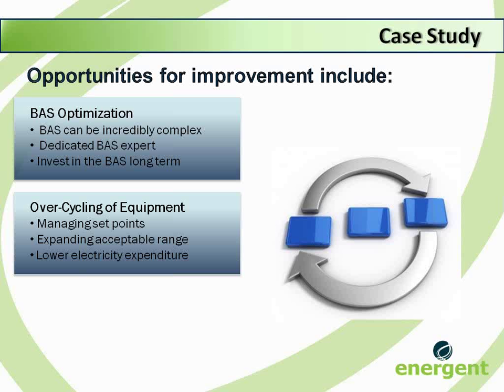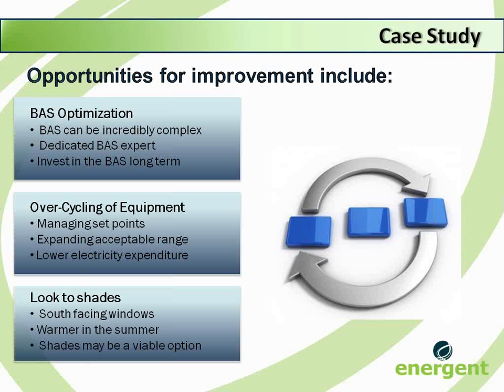When there's a narrow band for the measured variable, equipment tends to be cycled on and off frequently. This can cause an increase in energy expenditure as equipment ramps up to temperature, and often these large pieces of equipment are not built to cycle on and off all the time. It can really reduce the life expectancy of large capital equipment.